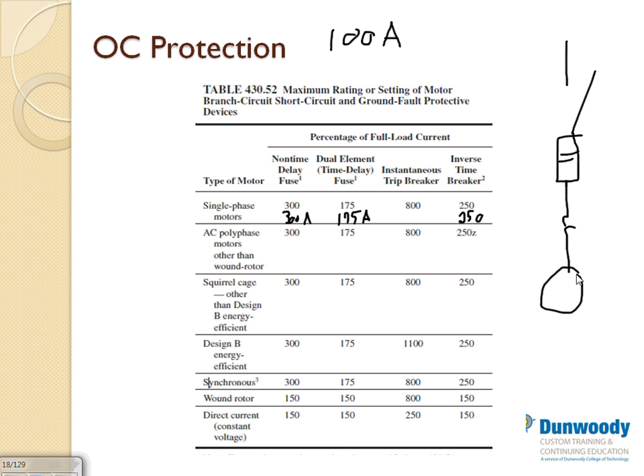Instantaneous trip circuit breakers are also called motor circuit protectors. Cutler-Hammer has them. All manufacturers make them. It's a special type of breaker that looks only at short circuit. Instead of having a full breaker with a thermal component, thermomagnetic has a thermal component and a magnetic component. What they do is they have just the magnetic component, so it's cheaper equipment, and they install it. That's why it's 800. So I need an 800 amp instantaneous trip circuit breaker. By the way, this is not a fake circuit breaker. Size-wise, it looks probably exactly like a 250 circuit breaker, but it's designed differently. Has anybody seen them, where you set it at A or B or C, adjusting by letters? That's basically just protecting from short circuit. No overload whatsoever on that circuit breaker.